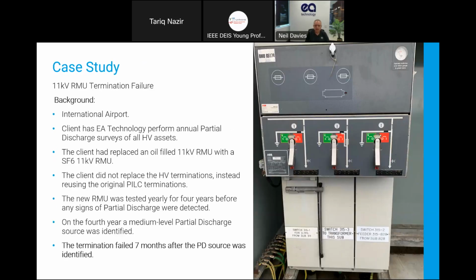Okay, so let's have a look at a couple of the case studies so that we can see how the different scenarios would play out. The first one here is on an 11 kV ring main unit. It's in an airport. The network had done annual partial discharge surveys of all their HV assets, and in this particular instance, they'd replaced an oil-filled 11 kV ring main unit with this SF6 ring main unit.